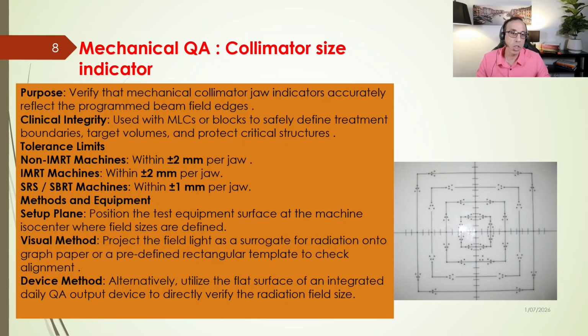However, for high precision SRS and SBRT machines, that tolerance tightens significantly to within plus minus 1 millimeter per jaw. To perform these checks, we position our testing surface directly at the machine isocenter. We can use a visual method, projecting the field light onto graph paper and seeing the deviation between our graph paper borders and the field light, or a predefined template. As you can see here, we have a template showing different field sizes. And we can use this template as a surrogate for the beam.